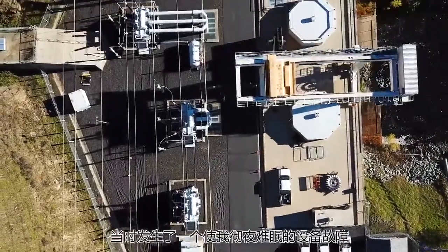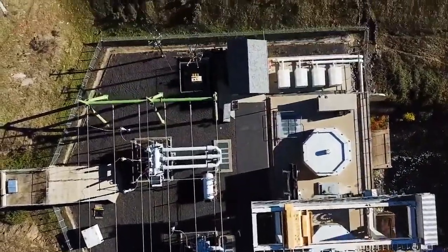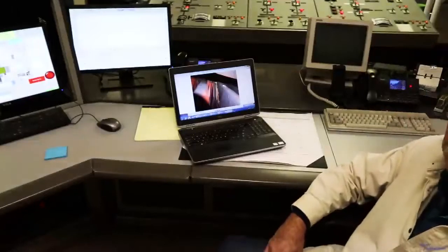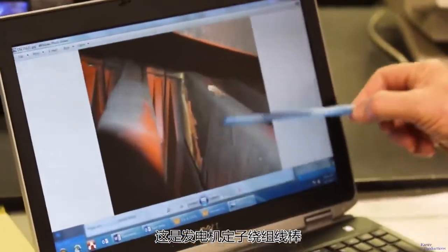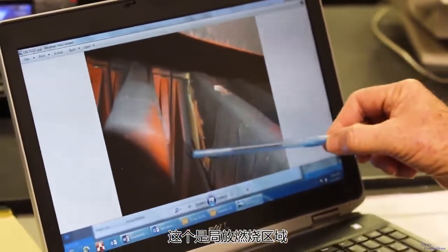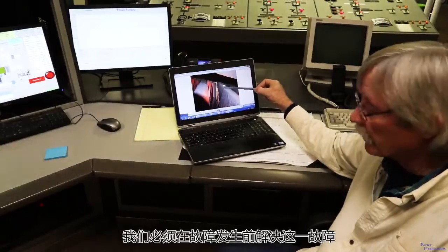The things that keep me up at night are equipment failures. That's a burn spot. This is a generator stator winding roebel bar — this is a partial discharge burn area. We have to repair this before we have a failure.